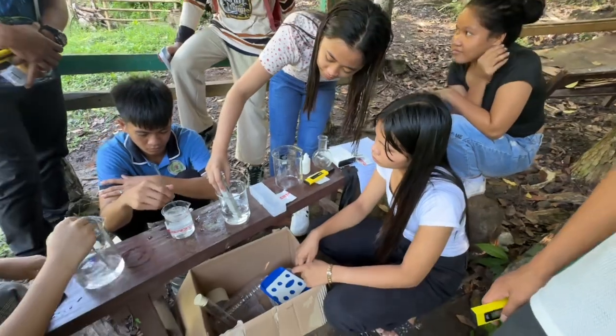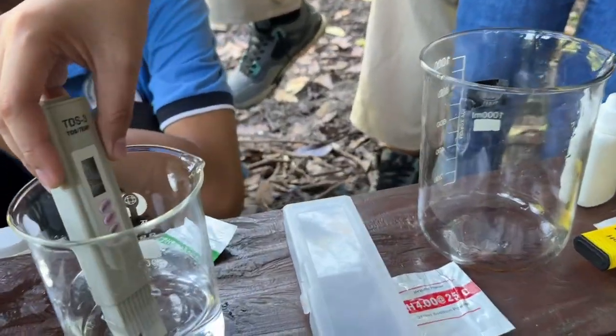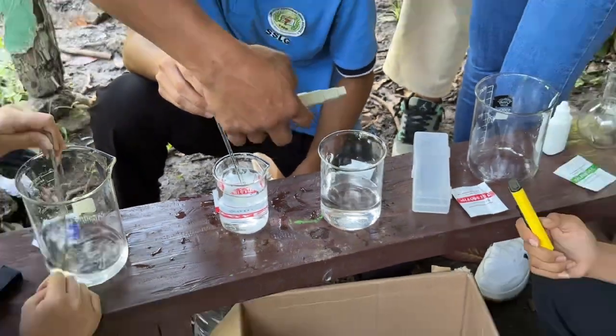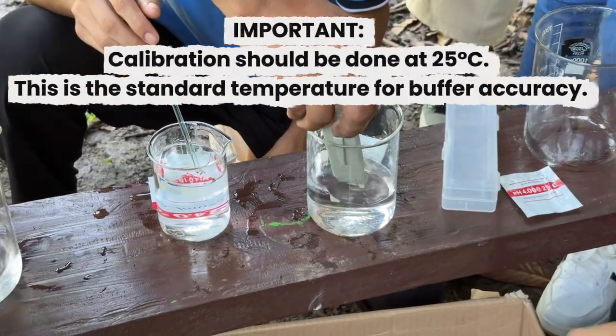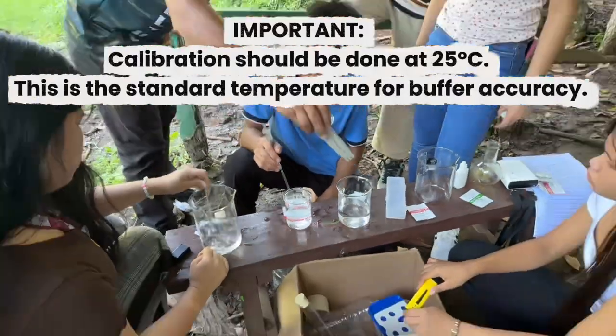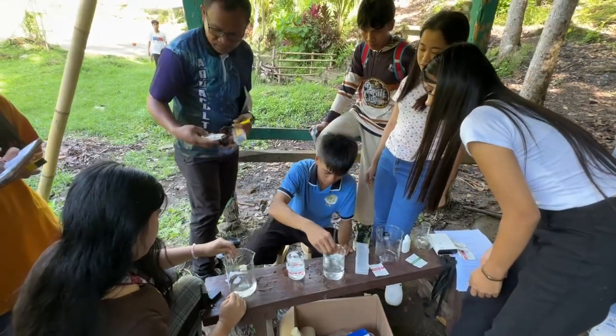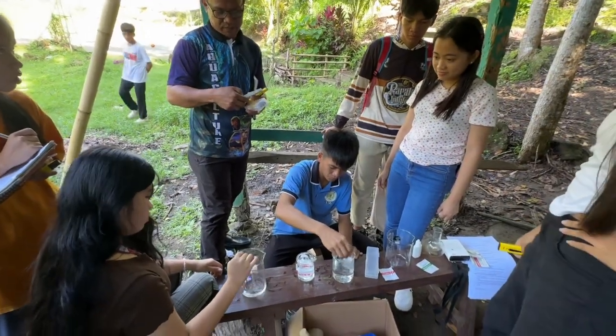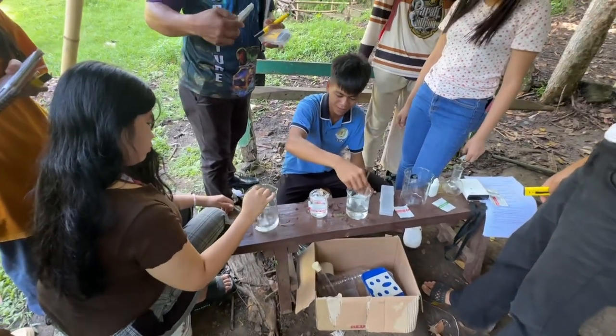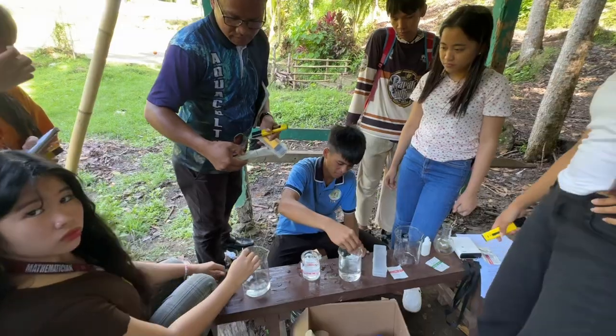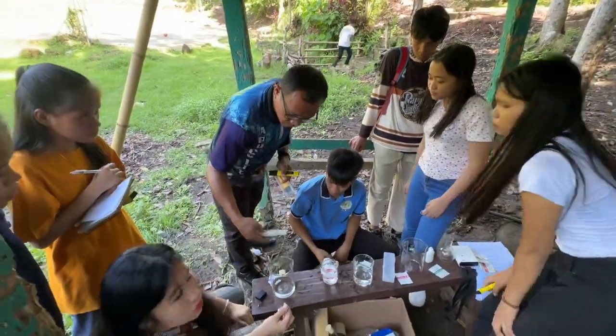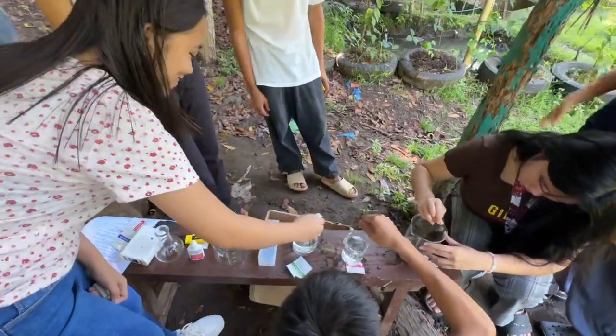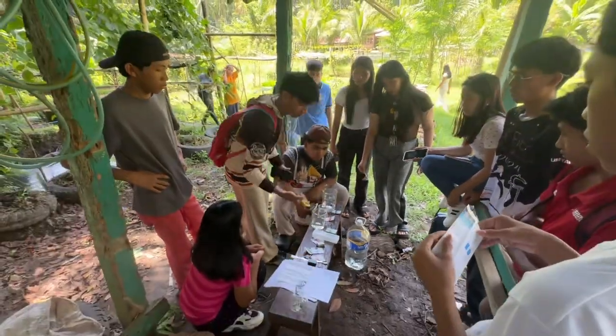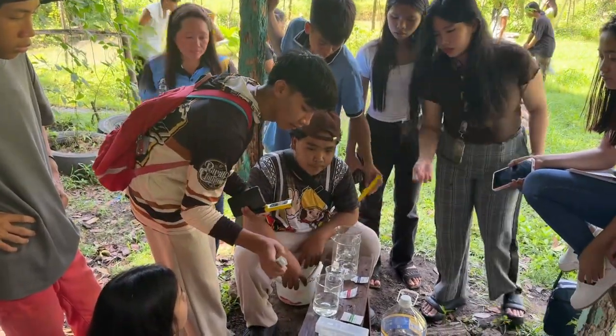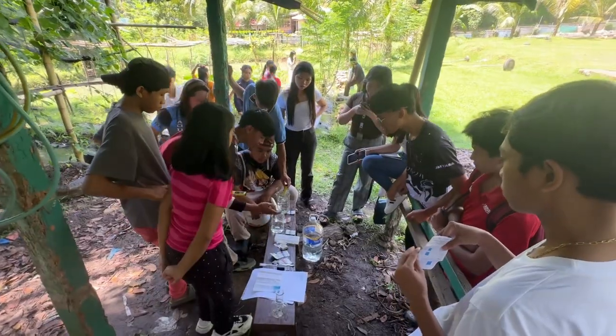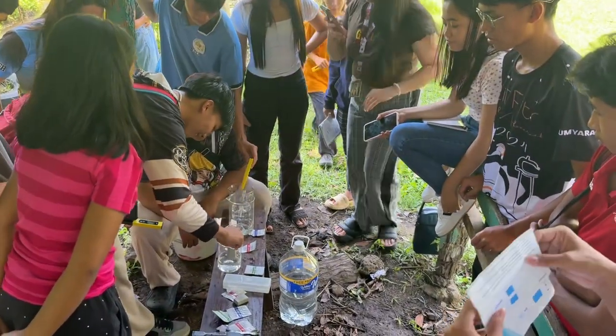Each buffer powder is dissolved in 250 milliliter distilled water. Important: calibration should be done at 25 degrees Celsius. This is the standard temperature for buffer accuracy. If your buffer solution is not at 25 degrees Celsius, don't worry. On the back of every buffer powder packet, there is a table showing the correct pH value for different temperatures. For example, at 20 degrees Celsius or 30 degrees Celsius, the buffer's exact pH value slightly changes. So always check the temperature and match it with the correction chart.